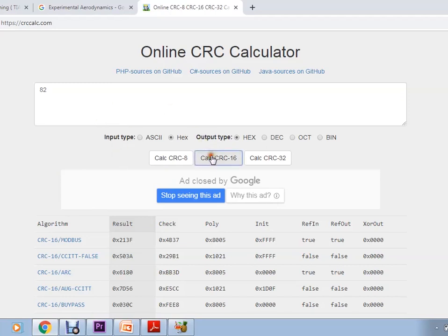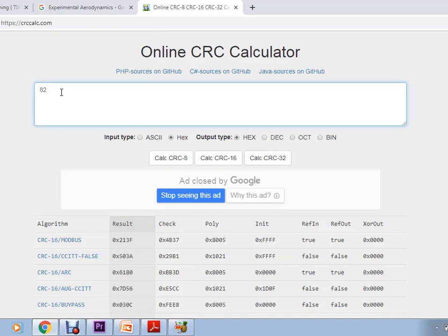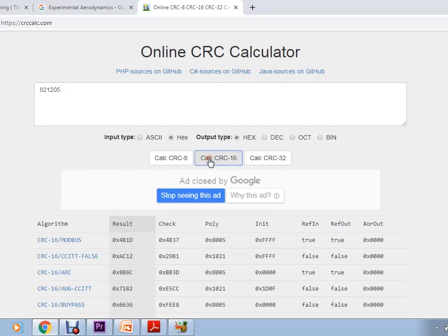Here we are verifying the 16-bit CRC. The input value taken in the example is 0x82 in hexadecimal. The Modbus CRC 16-bit result is 0x213F, which matches what we calculated. Similarly, you can add any number of bytes — hexadecimal or ASCII. Here we selected hexadecimal, and for three bytes the CRC changes to 0x4B1D. This way you can manually calculate and verify the CRC against the website value.